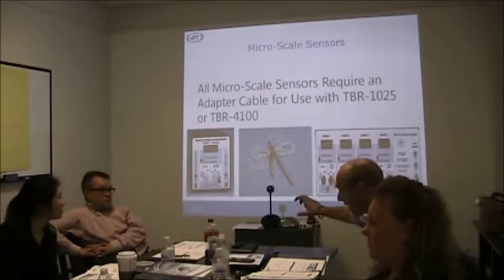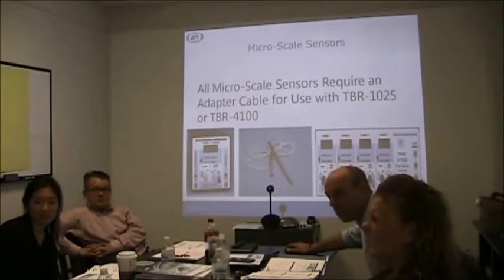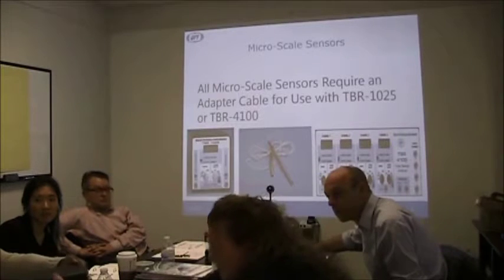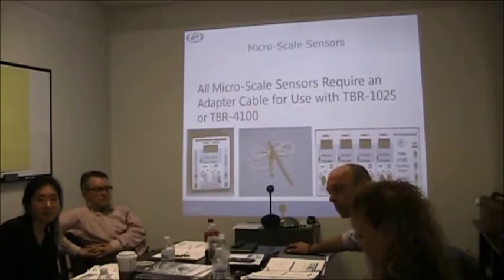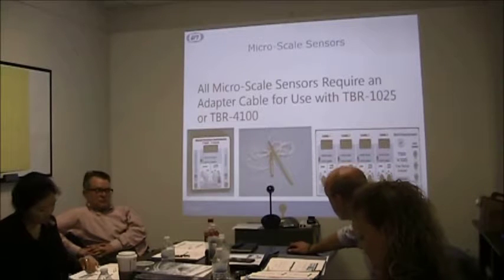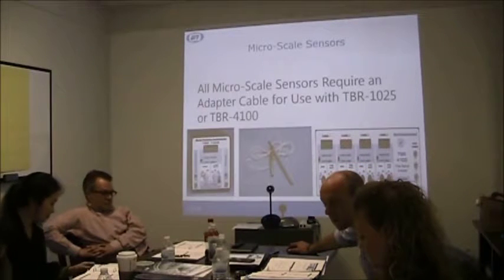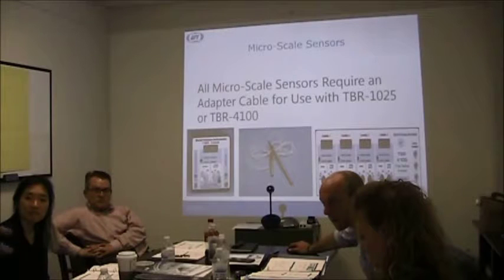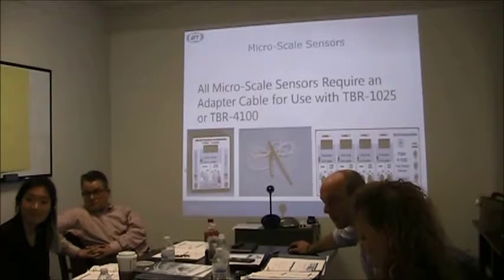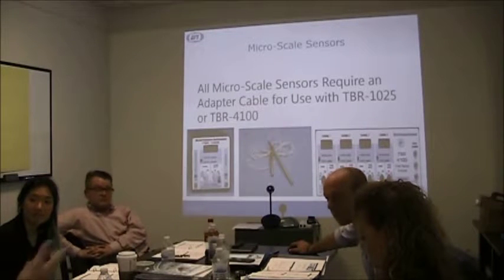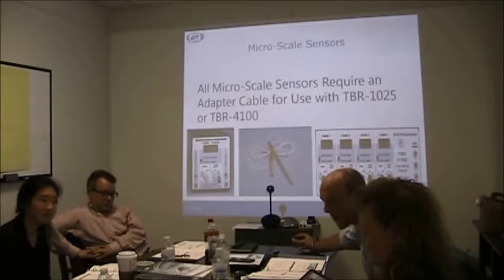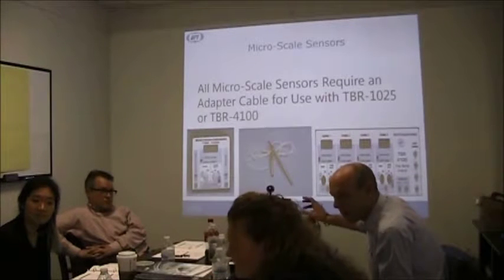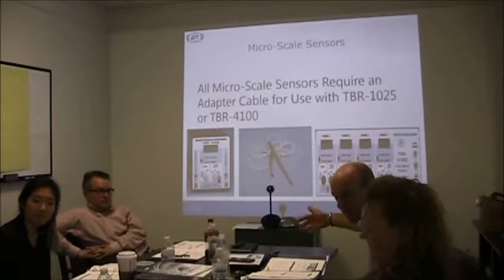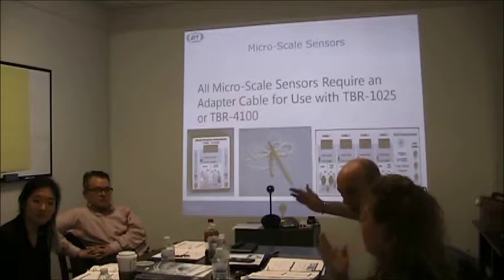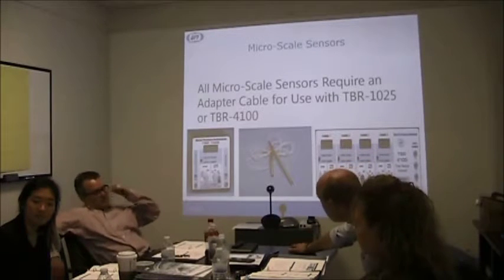So if you misselect, it's not giving a problem? No, the only thing is the display on your data acquisition system, where your units will change based on it. If you're in the 1 microamp range, for example, you may see on the display 0.015. So you know that if you switch that to 100 nanoamps, it's going to be 0.15 on the display. You just factor a 10. So it's only the scale. Correct. It's always measuring the same, but you want to see it in a resolution that you can really see, based on the responsiveness.